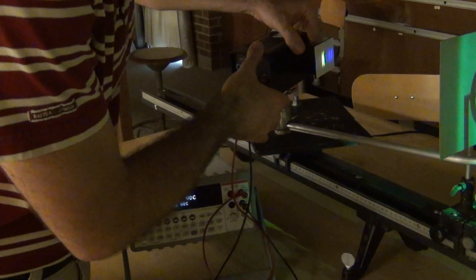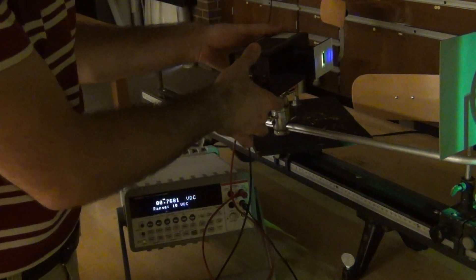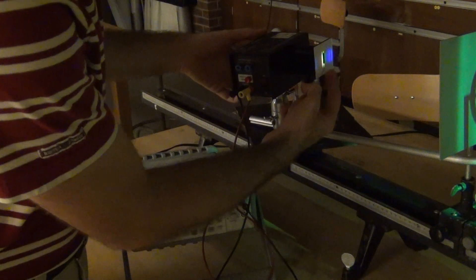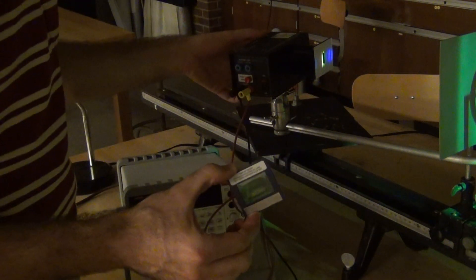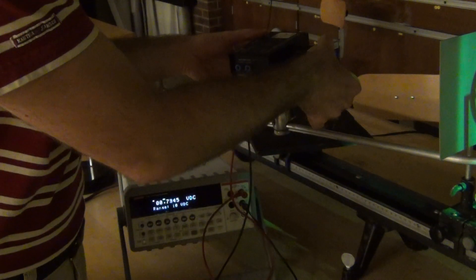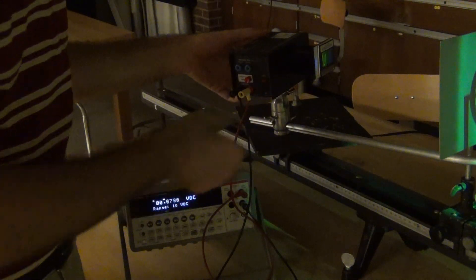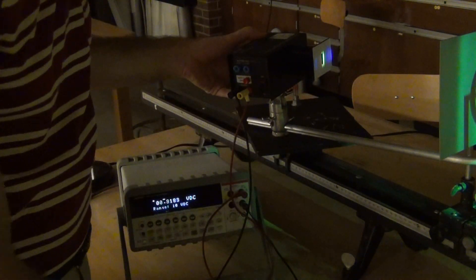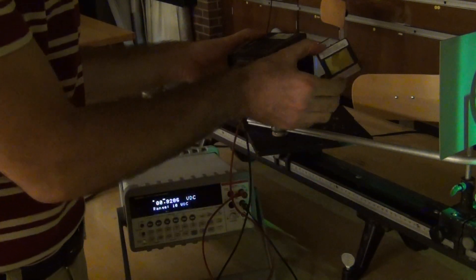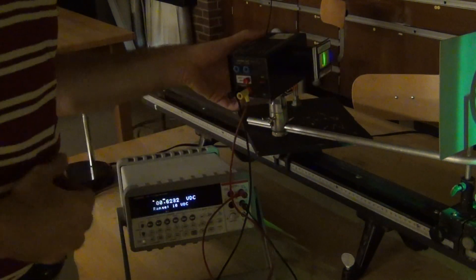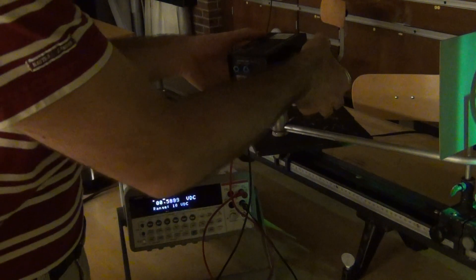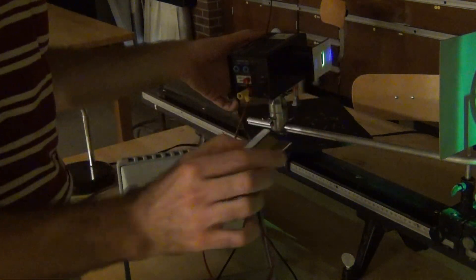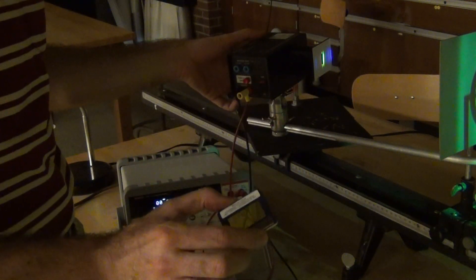You are then ready to adjust to a different color. When you measure the green, you'll want to use a green filter which sticks on the front via magnets. When you measure the orange, you'll want to use an orange filter which also sticks on the front via magnet. Those low energy wavelengths, we want to filter out any spurious light.